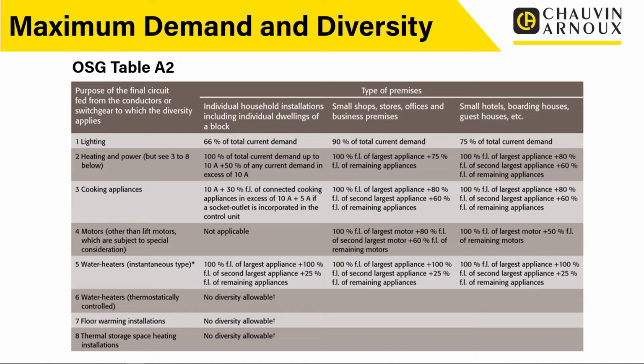What this does is it says, if we've got some heat and power circuits, we take 100% of the first one plus 75% of the remaining appliances, and we work out our maximum demand in that approach. But again, it's quite old. These things have been in here a long time. They don't really take into account modern usage of electrical installations, modern lighting for example, the changes in loads. Motor drives and all these sort of things aren't really taken into account in this table.